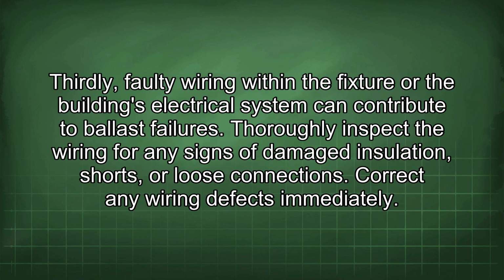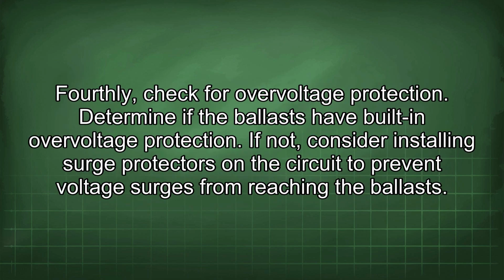Thirdly, faulty wiring within the fixture or the building's electrical system can contribute to ballast failures. Thoroughly inspect the wiring for any signs of damaged insulation, shorts, or loose connections. Correct any wiring defects immediately. Fourthly, check for overvoltage protection. Determine if the ballasts have built-in overvoltage protection. If not, consider installing surge protectors on the circuit to prevent voltage surges from reaching the ballasts.